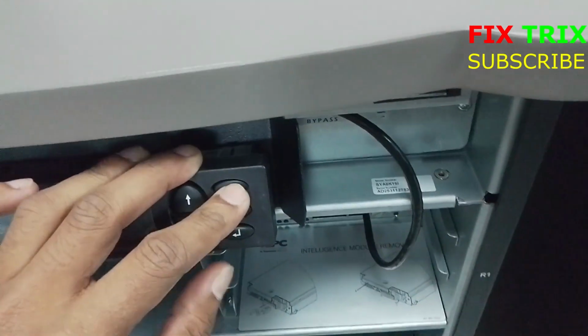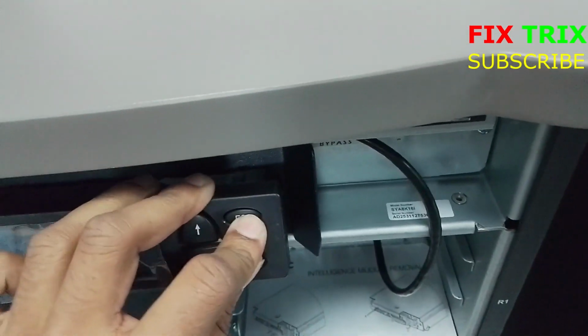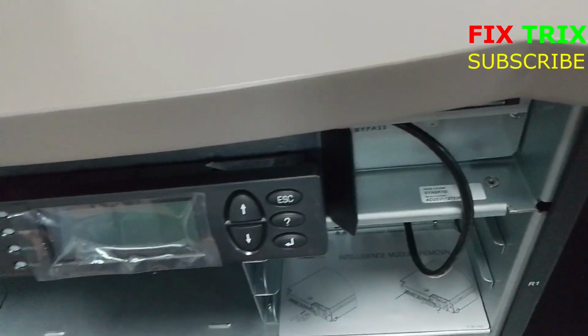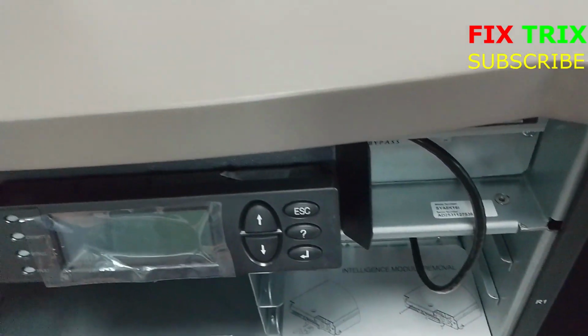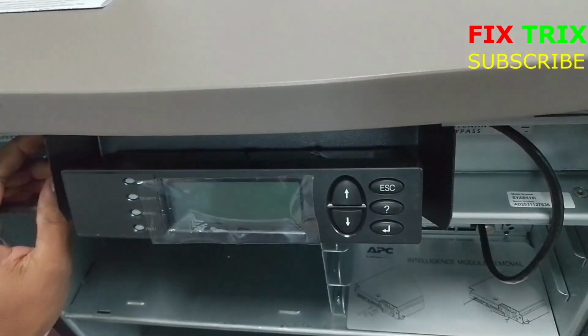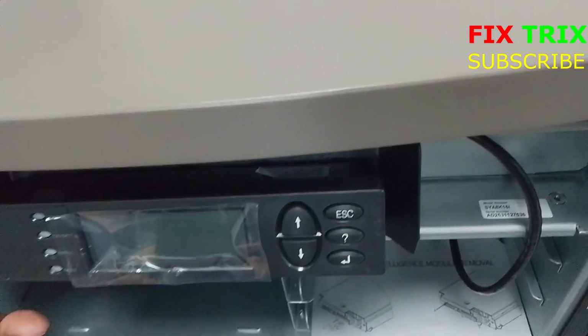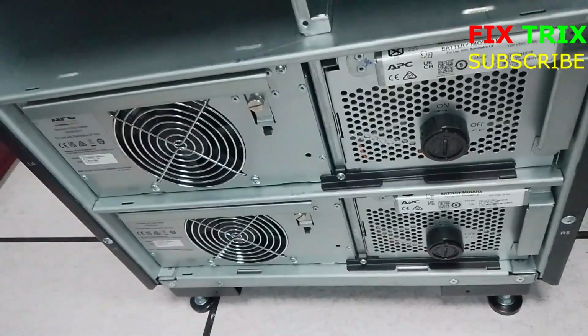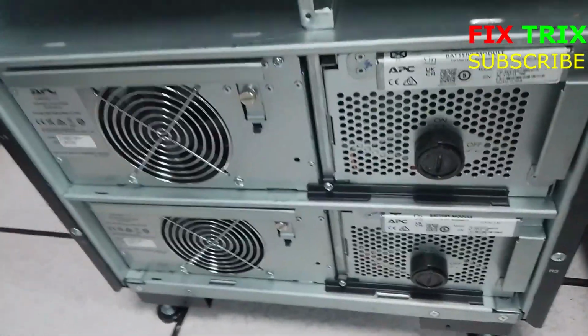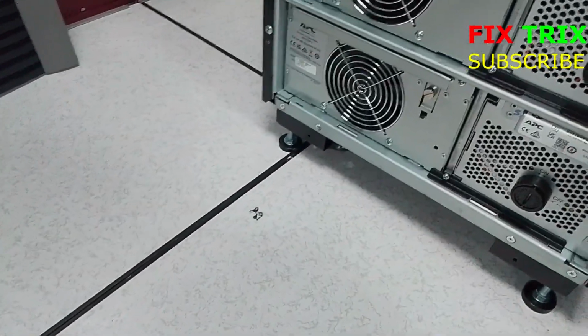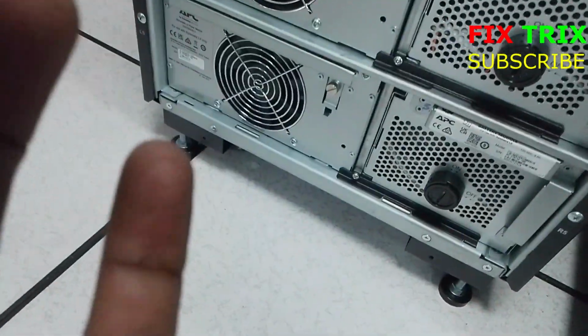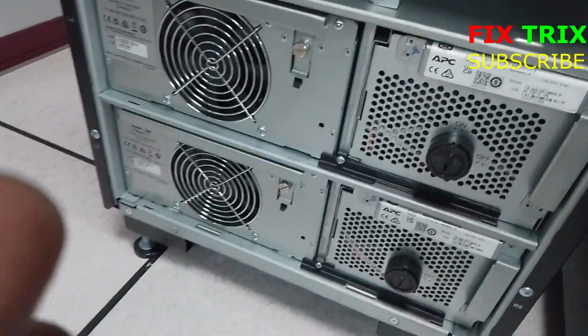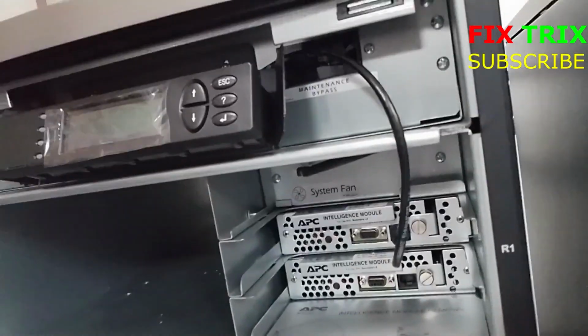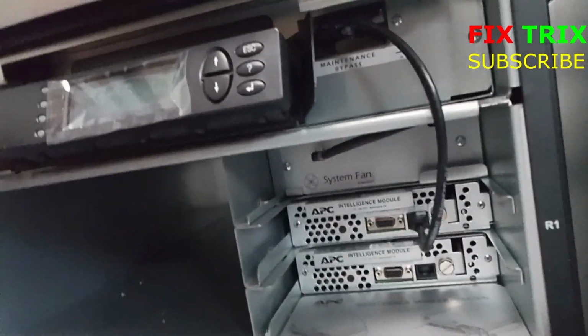Now we turn on the UPS. At this moment the UPS has only 2 power modules and 2 battery modules installed. This is enough for the UPS to start and operate safely. First we turn on the utility power feeding the UPS. Now the UPS has incoming AC supply available. Next we turn on the input circuit breaker. This allows the utility power to enter the UPS.